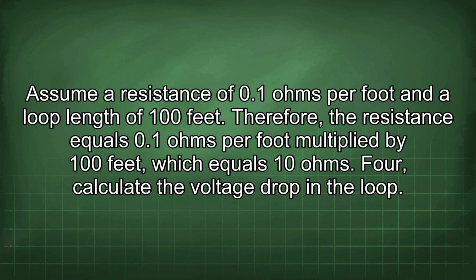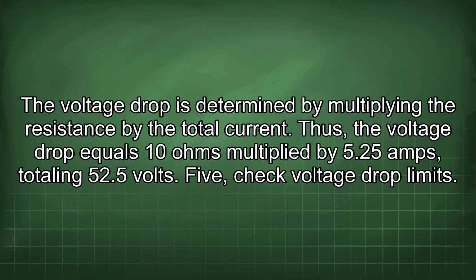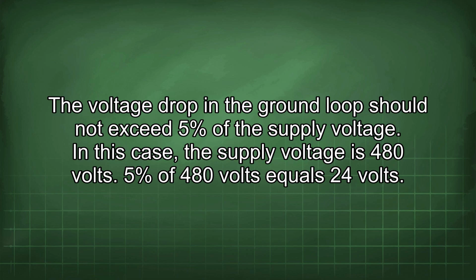4. Calculate the voltage drop in the loop. The voltage drop is determined by multiplying the resistance by the total current. Thus, the voltage drop equals 10 ohms multiplied by 5.25 amps, totaling 52.5 volts. 5. Check voltage drop limits. The voltage drop in the ground loop should not exceed 5% of the supply voltage. In this case, the supply voltage is 480 volts. 5% of 480 volts equals 24 volts.